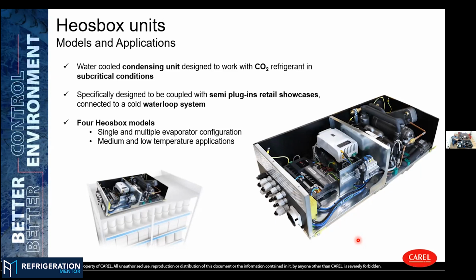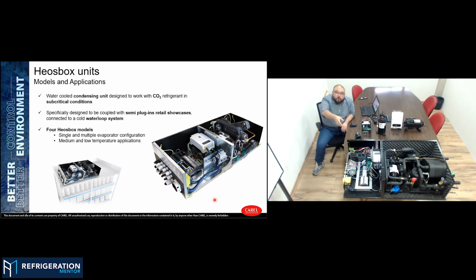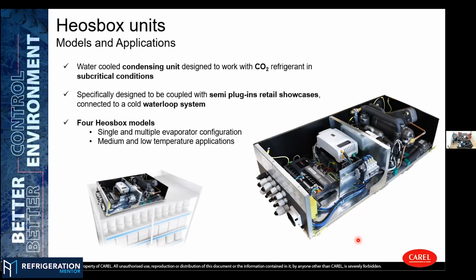It's a water loop condensing unit running at subcritical applications where we can use these kinds of compressors, vertical or horizontal. In this case, it's a horizontal one. You can use the available chilled water that you have in your installation to reject all the heat from the installation. So the idea here is that we have a very low height unit that you can place on top of a showcase or on top of a cold room, and you can make the refrigeration circuit very close, the condensing unit to the evaporator. So in this case, you can reduce refrigerant charge, you can maximize the efficiency, and you have a micro-distributed system.